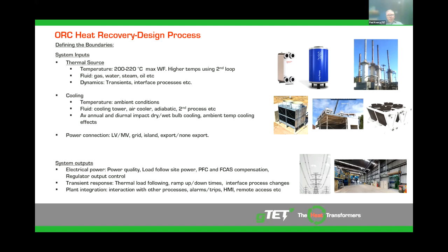the output. Various aspects must be considered on the power connection, such as voltage, whether you're setting it up for grid or island mode, whether you're going to export or not export power, with many of these aspects dictated by the respective power authority. The output boundaries to be considered include one, for power, the power quality, which in Australia is typically AS4777 for embedded power generation, power factor correction and FCAS compensation, and what controls that the power authority may want over the generating system.